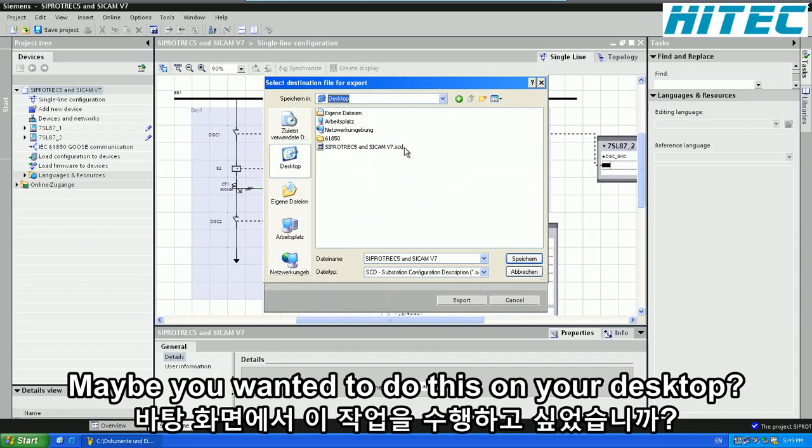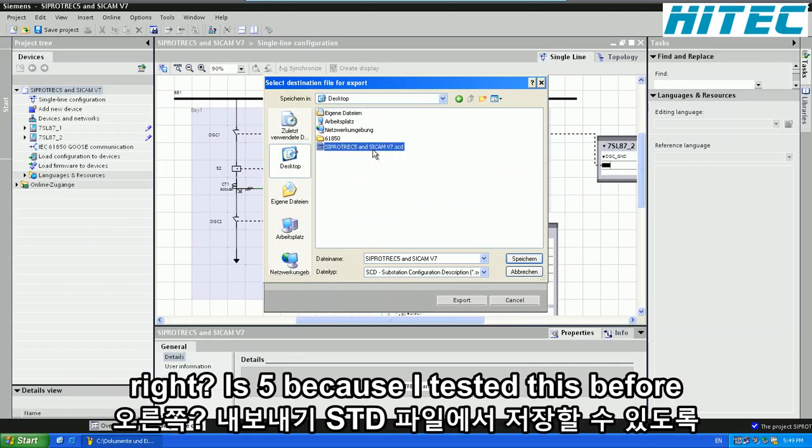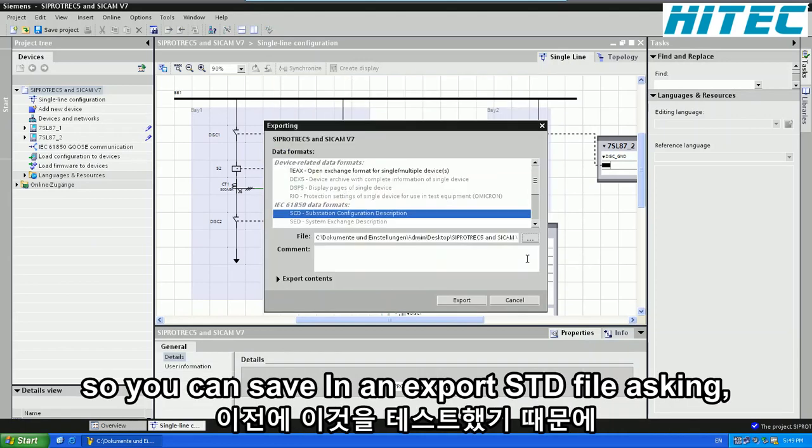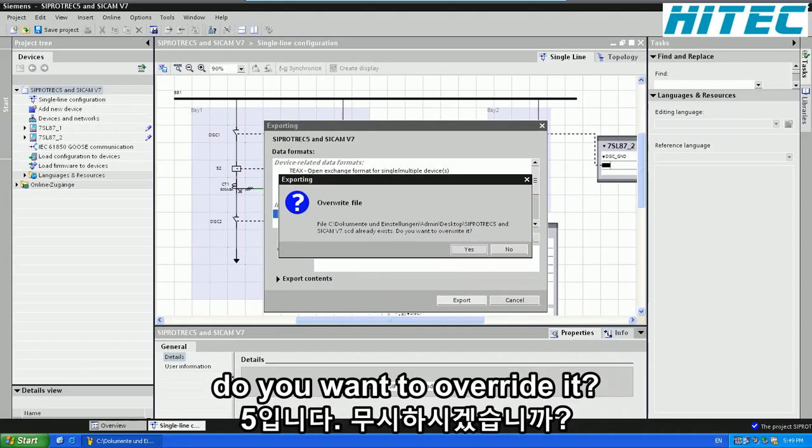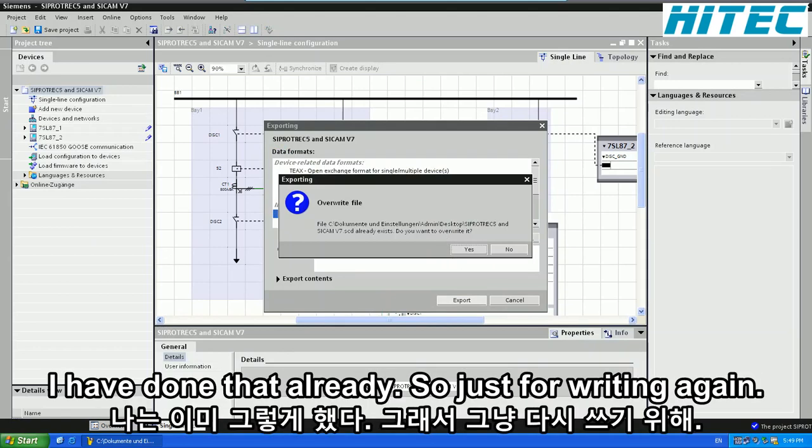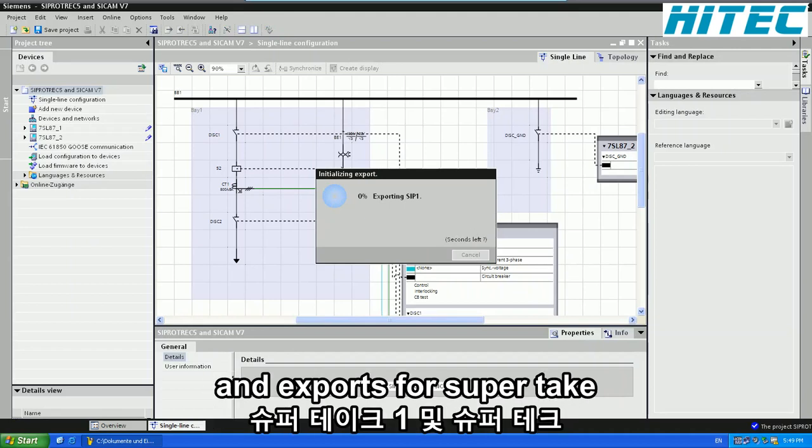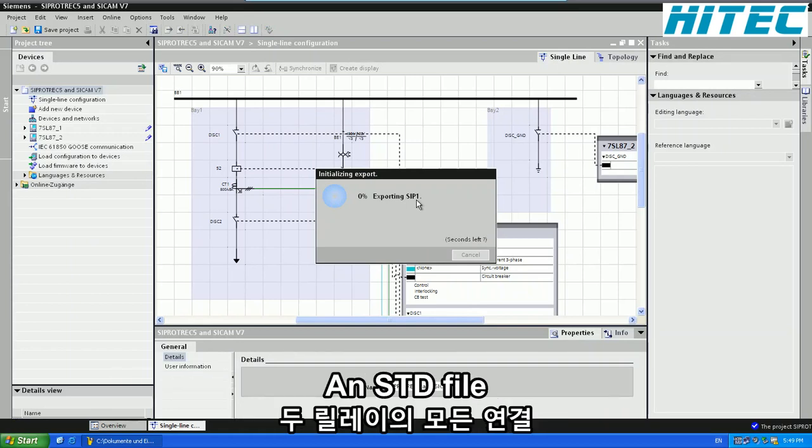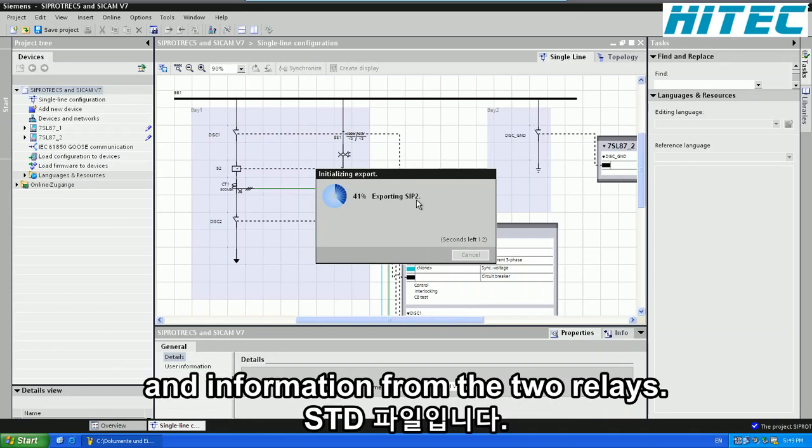Maybe you want to do this on your desktop. So I will just overwrite this file because I tested this before. So you say save and then export the .scd file. It asks you do you want to overwrite it. I have done that already. So just overwrite it again so you have only one unique file. It exports for SIPROTEC 1 and SIPROTEC 2 for the two devices an .scd file with all the connections and information from the two relays.